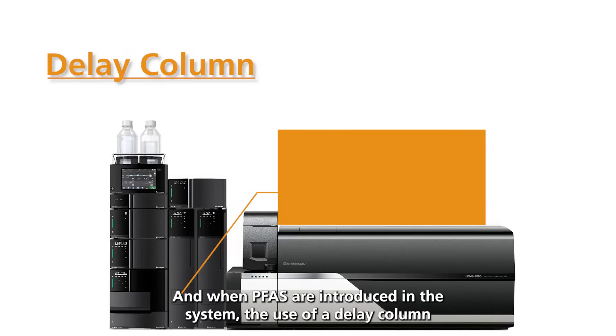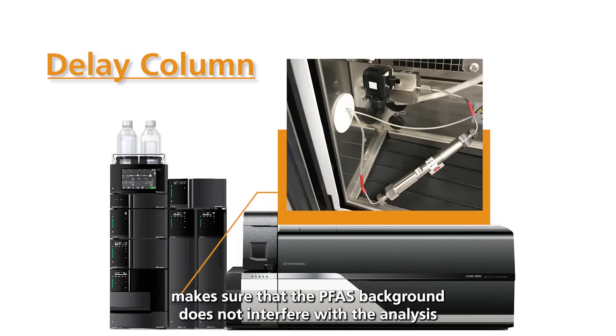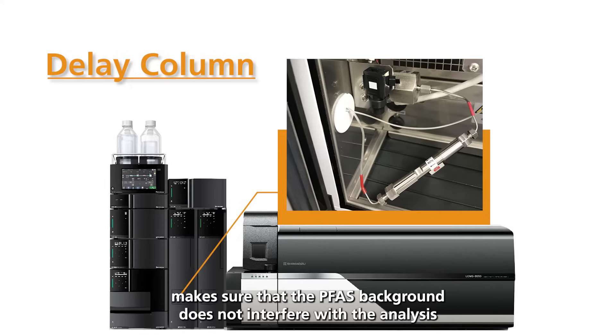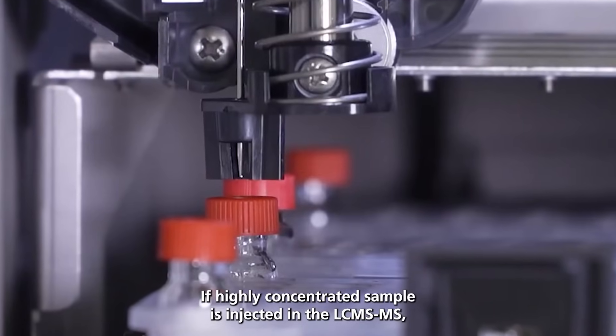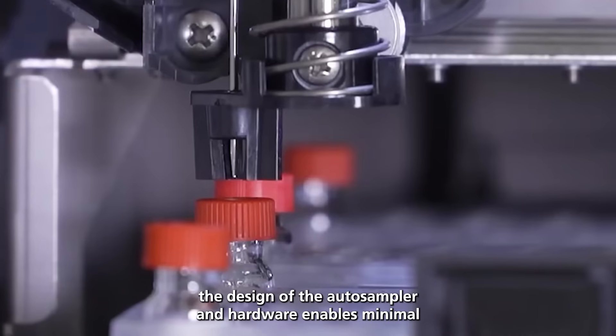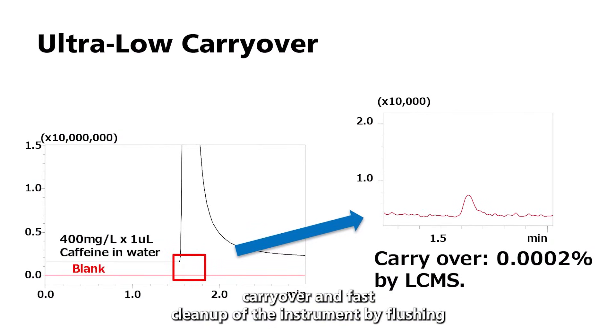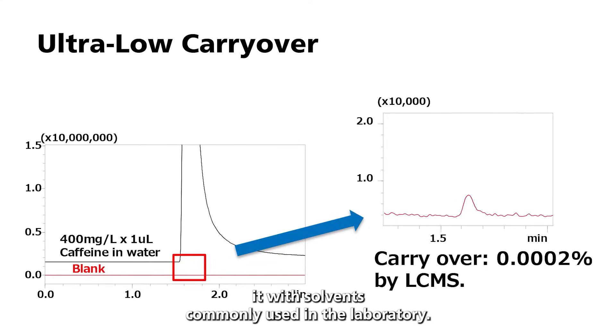And when PFAS are introduced in the system, the use of a delay column makes sure that the PFAS background does not interfere with the analysis. If a highly concentrated sample is injected in the LC-MS-MS, the design of the autosampler and hardware enables minimal carryover and fast cleanup of the instrument by flushing it just with solvents commonly used in the laboratory.